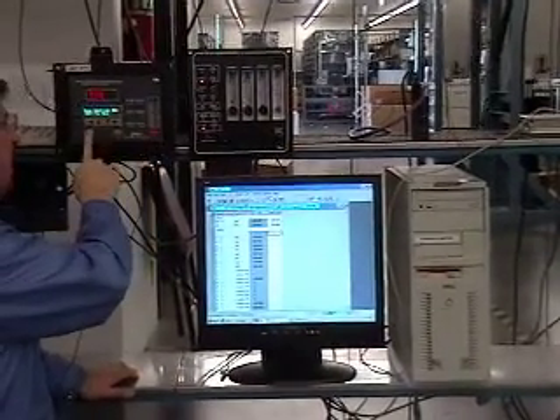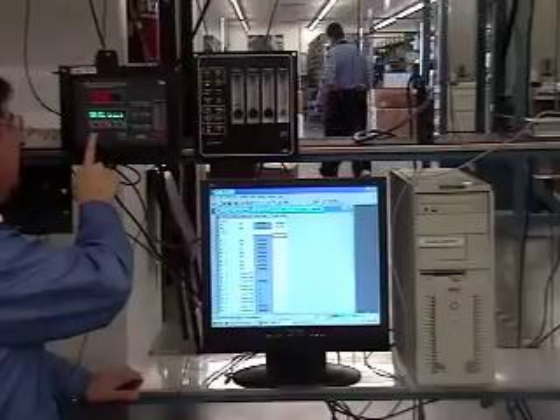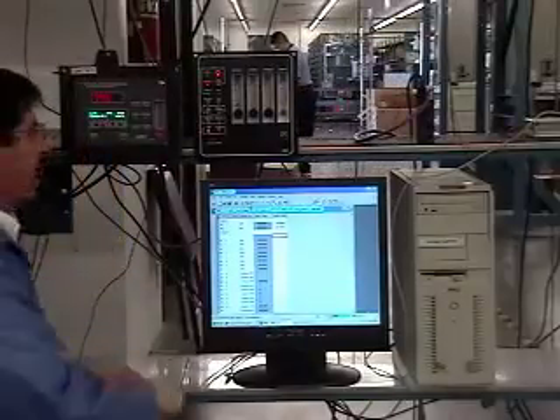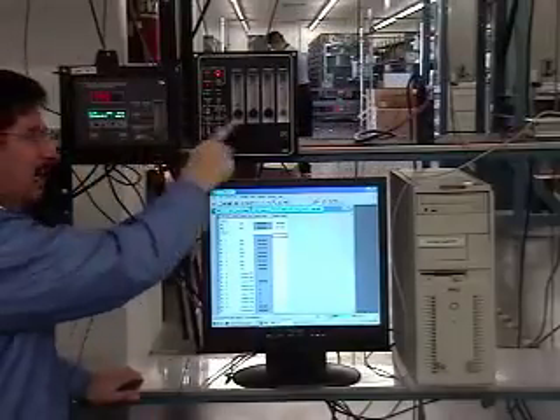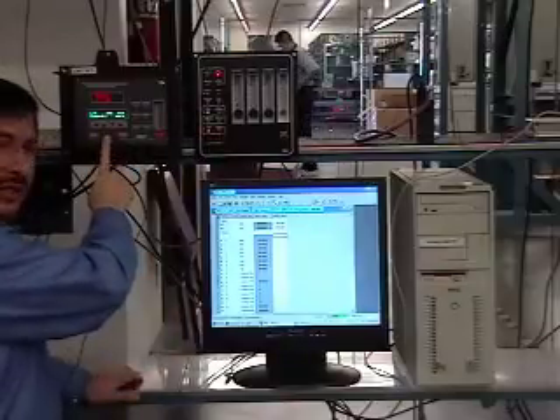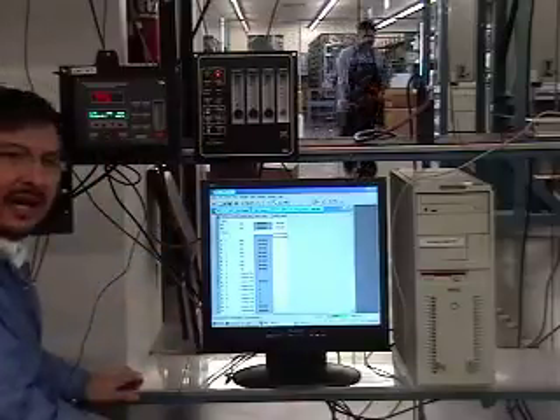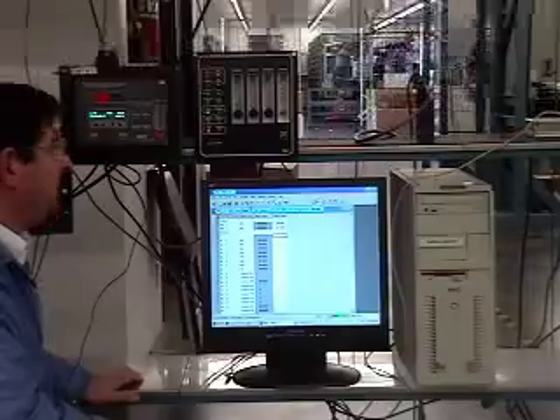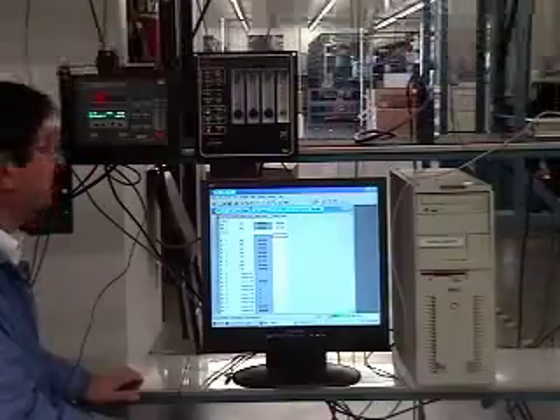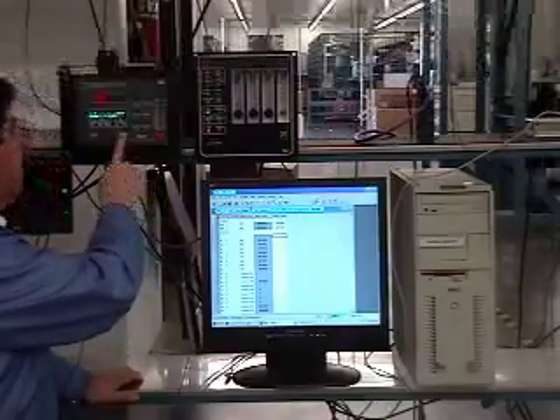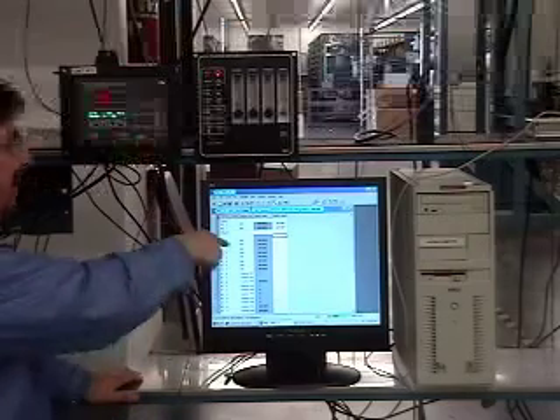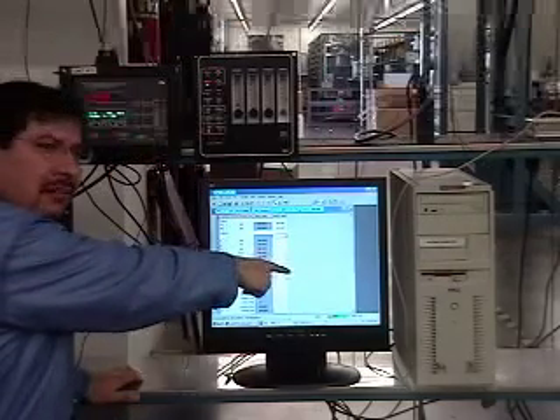In this mode, the analyzer has control. I can put the analyzer on span and look at that way. Now the analyzer can control the BB1. I told the analyzer to go into span, and it changed the valve in the BB1. I'm going to escape now. It's going back to the previous, because I can still send commands through the Profibus network.